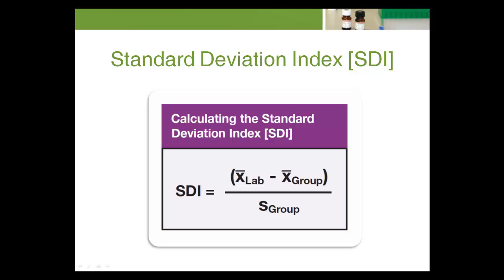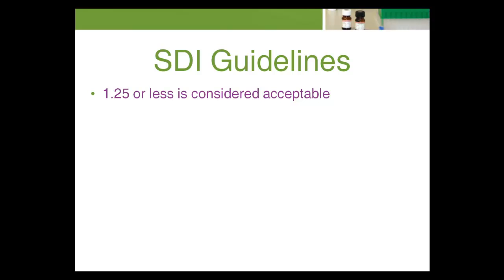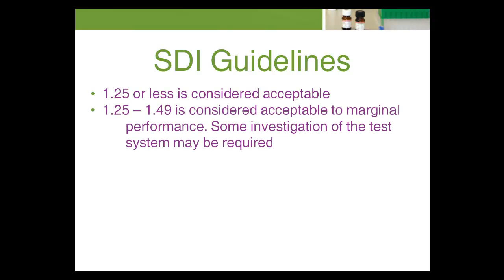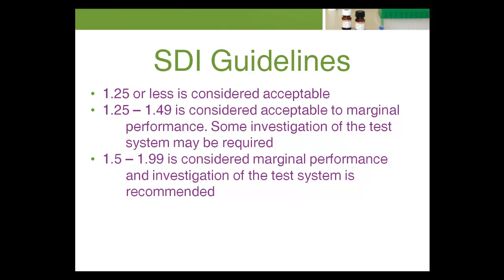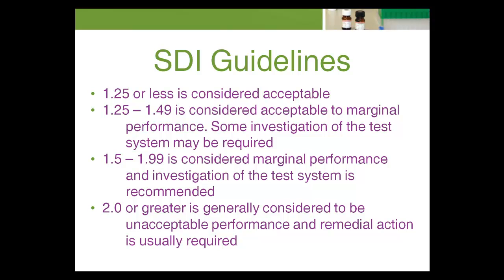Now let's move on to the Standard Deviation Index (SDI). SDI is a peer-based estimate of reliability. If the peer group mean is defined as mean-group, the standard deviation as S-group, and the laboratory's mean as mean-lab, the target SDI is zero, which indicates a perfect comparison with the peer group. The following guidelines may be used with SDI: a value of 1.25 or less is considered acceptable; 1.25 to 1.49 is acceptable to marginal performance and some investigation may be required; 1.5 to 1.99 is marginal performance and investigation is recommended; 2.0 or greater is generally considered unacceptable performance, and remedial action is usually required.